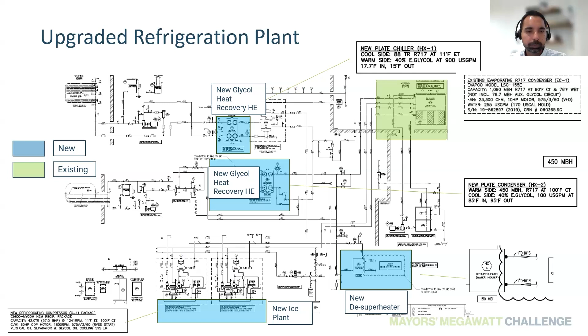Kathryn, can you go to the next slide? This is just a schematic for everyone to consider, but we already touched on that. You have a new ice plant at the bottom of the screen, everything in blue is new. There's a new desuperheater, which provides heating for your domestic hot water, and a glycol heat exchanger, which provides heating for your air handling units. Your existing cooling tower still remains at this point, since it's 2019, so we are not changing that one.